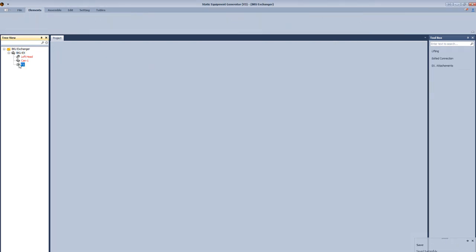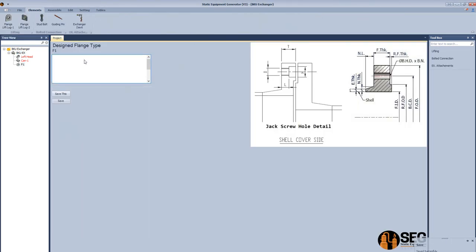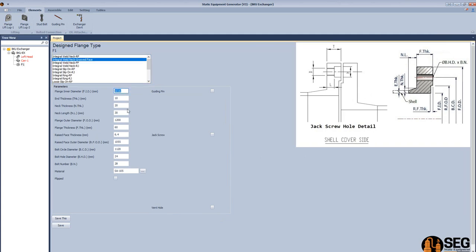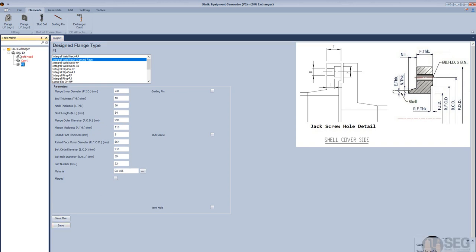Now we will add a designed flange for the heat exchanger. We will select the second type, which is integral weld neck with grooved face. Define the inside diameter of this flange, the thickness of the end, the neck thickness, and the neck length. After that, we will define the outside diameter of the flange, the flange thickness, the raised face thickness, the raised face outside diameter, the bolt circle diameter, and the bolt diameter. After that, number of bolts, and we will click save.